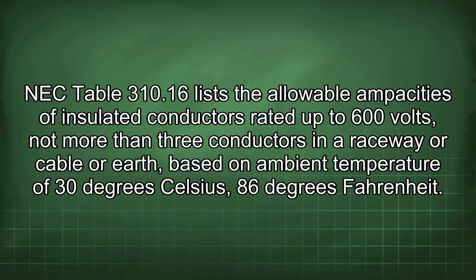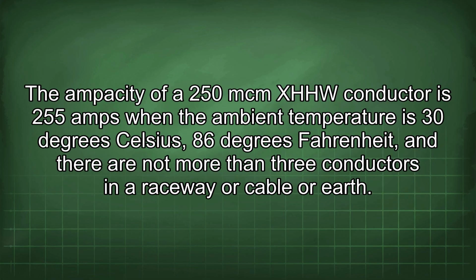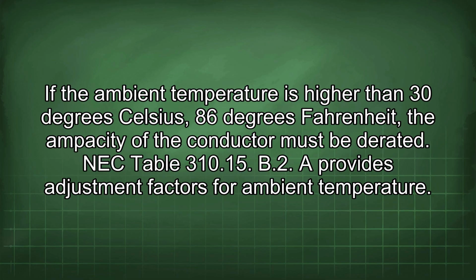NEC Table 310.16 lists the allowable ampacities of insulated conductors rated up to 600 volts, not more than 3 conductors in a raceway or cable or earth, based on an ambient temperature of 30 degrees Celsius, 86 degrees Fahrenheit. The ampacity of a 250 MCM XHHW conductor is 255 amps when the ambient temperature is 30 degrees Celsius, 86 degrees Fahrenheit, and there are not more than 3 conductors in a raceway or cable or earth. If the ambient temperature is higher than 30 degrees Celsius, 86 degrees Fahrenheit, the ampacity of the conductor must be derated. NEC Table 310.15(B)(2) provides adjustment factors for ambient temperature.